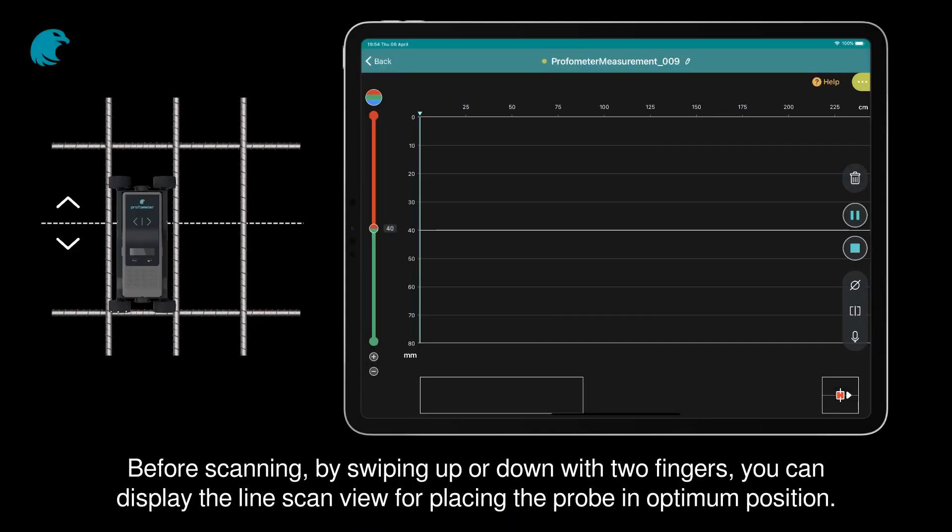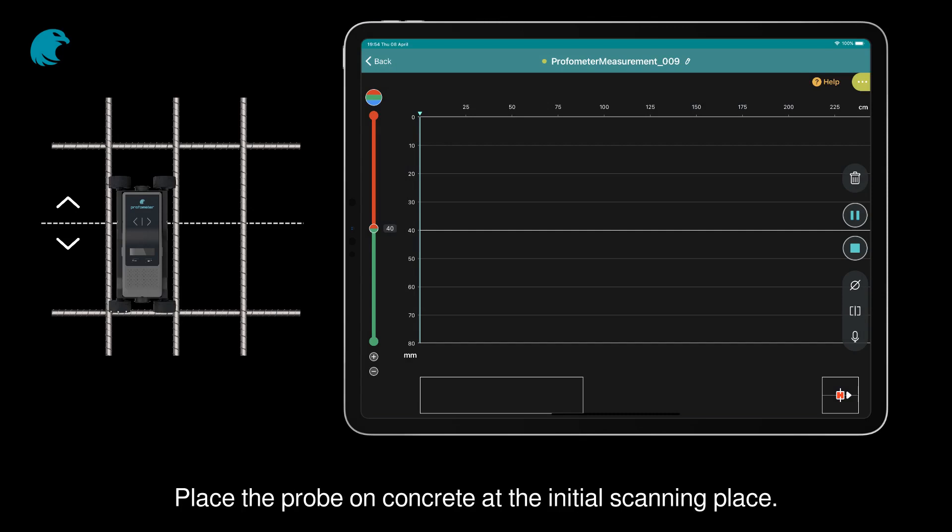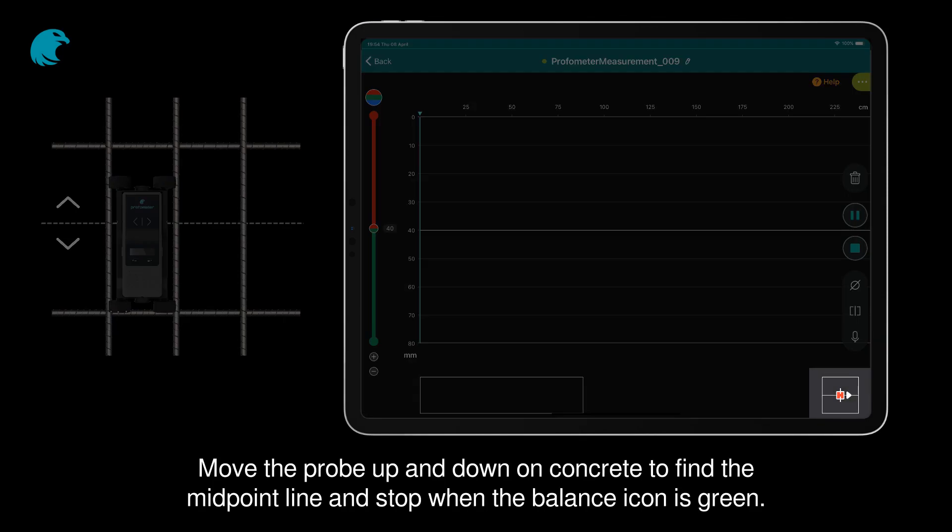Before scanning each line, by swiping up or down with two fingers, you can display the line scan view for placing the probe in optimum position. Place the probe on concrete at the initial scanning place. Move the probe up and down to find the midpoint line and stop when the balance icon is green.